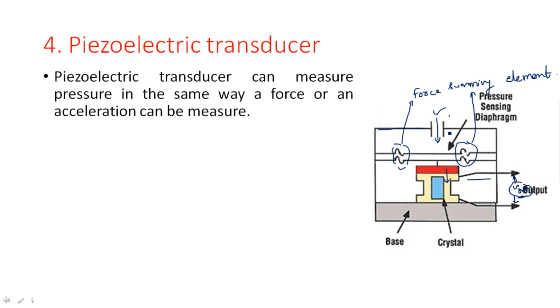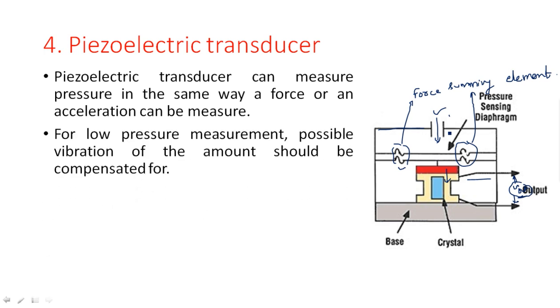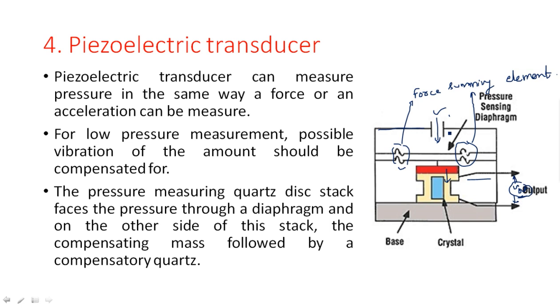Piezoelectric transducers can measure pressure; similarly, force or acceleration can be measured. For low pressure measurement, possible vibration of the mount should be compensated. The pressure-measuring quartz disc stack faces the pressure through a diaphragm. The quartz crystal shown in blue is placed on a strong base, and when compressed by the diaphragm, the output voltage varies.